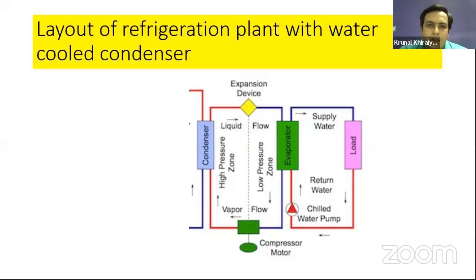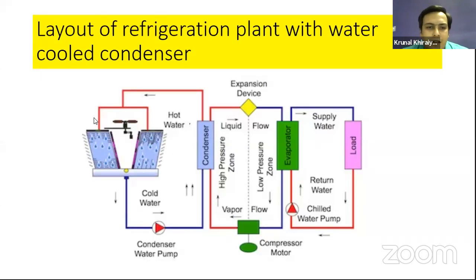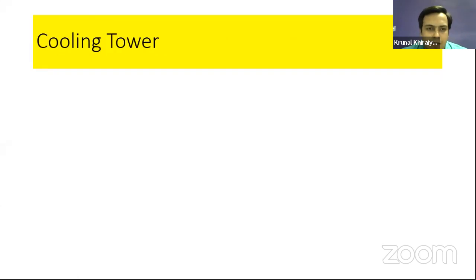So how can we generate cold water every time? For that we need an additional device, and that device, which is the focus of today's webinar, is the cooling tower. Here the hot water comes from the condenser and goes to the cooling tower, where it is cooled down; heat is rejected from the hot water and absorbed by the air which comes from the atmosphere. Again we get cold water. So this is the cycle and this is the layout of the plant, and that is why we require the cooling tower in different plants and refrigeration systems.